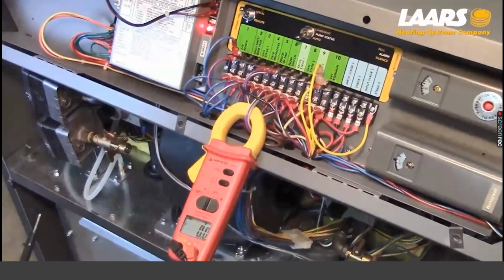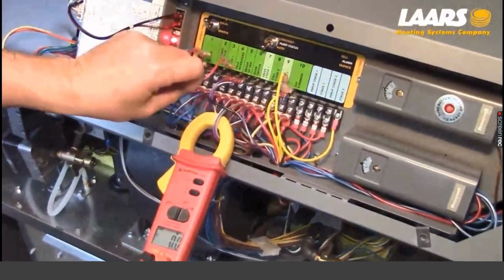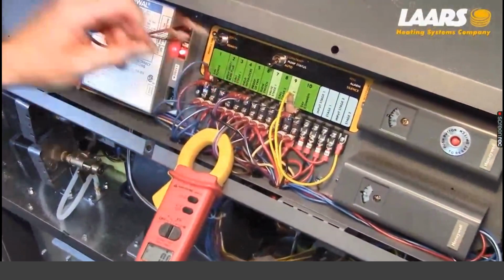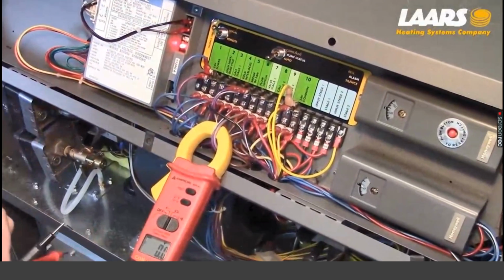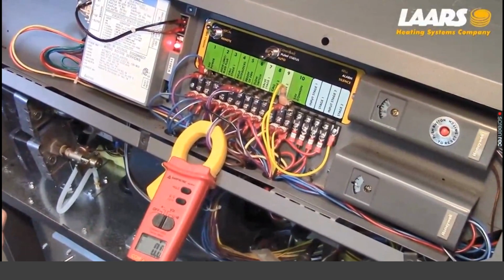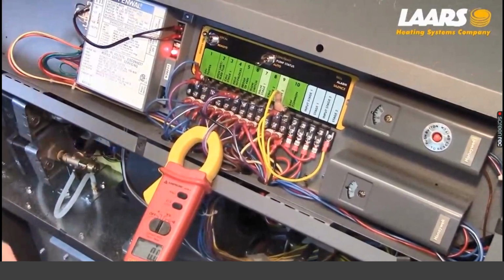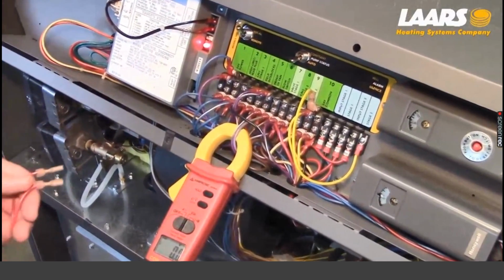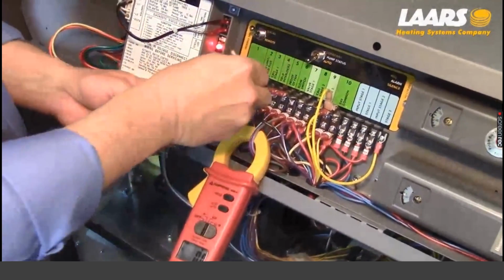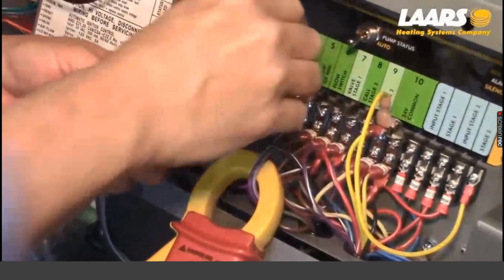This, as it leaves the factory, will have a jumper wire on terminal 3 and 4. However, in the field, you may have an aquastat or energy management may control this. If you're troubleshooting the boiler, remove your field connections and reconnect a jumper lead, okay?